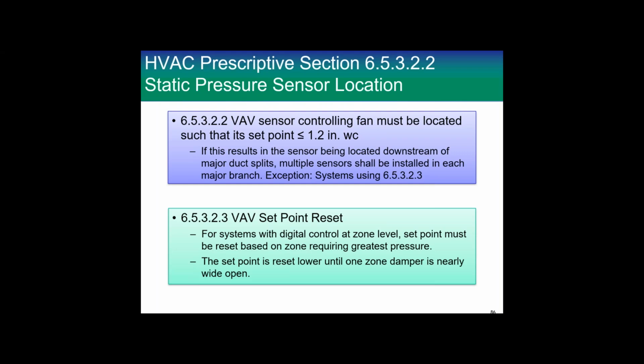That's where we want you to control your VAV fans. Now, because we have the set point reset, we just say the VAV sensor controlling the fan must be located such that its set point is less than or equal to 1.2 inches of water column. Now, this is a made up number. It doesn't make any sense. It's just that you have to have some place to start.